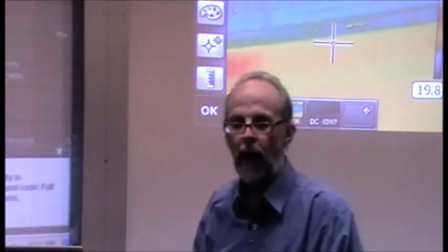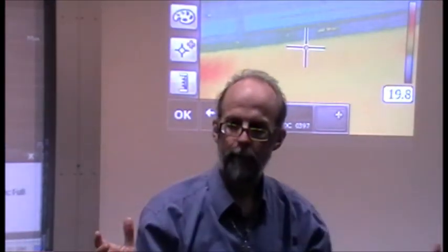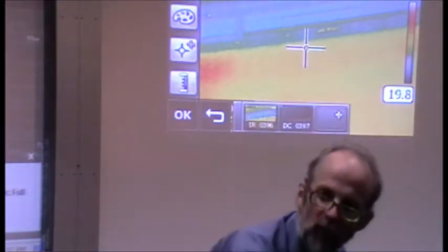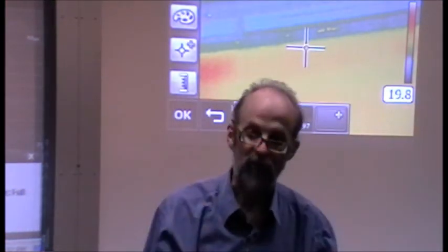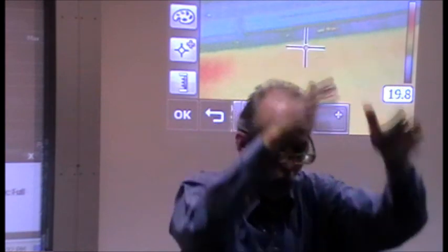It's a reflected temperature. Basically, if you're not quite sure where the sources of the reflections are, you take this crumpled piece of aluminium foil and then flatten it out again as well as you can. So you've just got an uneven surface. Because the aluminium foil on the bright side is very low emissivity, very high reflectance, you assume that there is no emissivity, and you basically do the same thing as if I was looking directly at the object. Yeah. So I either look at the source of the reflection or at the thing I want.